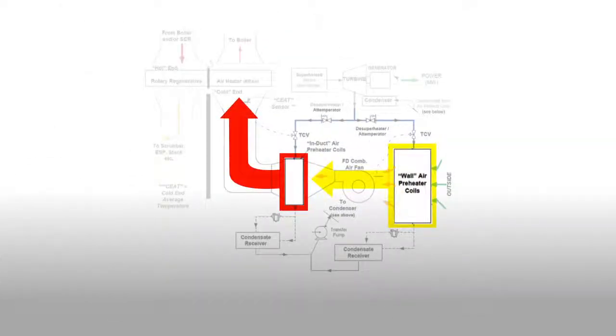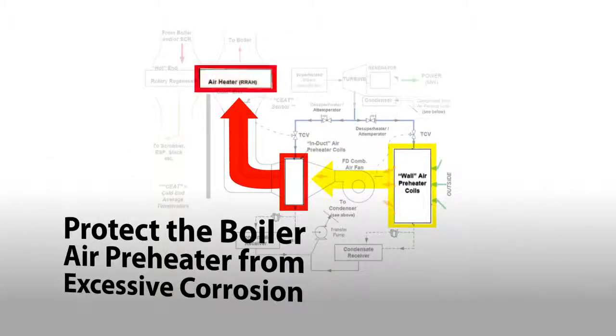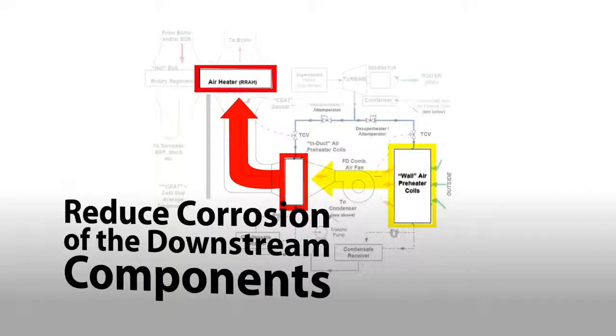Armstrong's steam and liquid air heater systems protect the boiler air preheater from excessive corrosion and fouling by controlling the cold end average temperature. This also reduces corrosion of the downstream components by maintaining the flue gas temperature above the acidic dew point at all times.